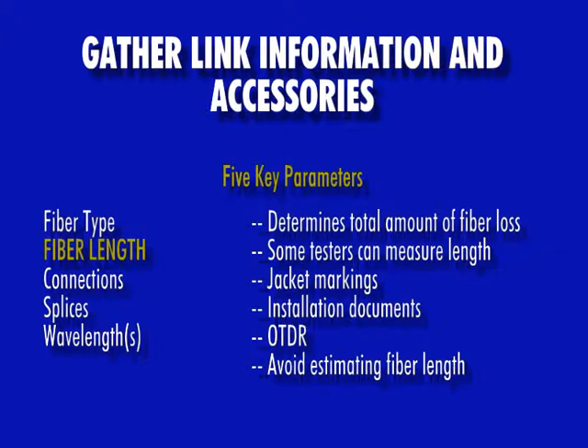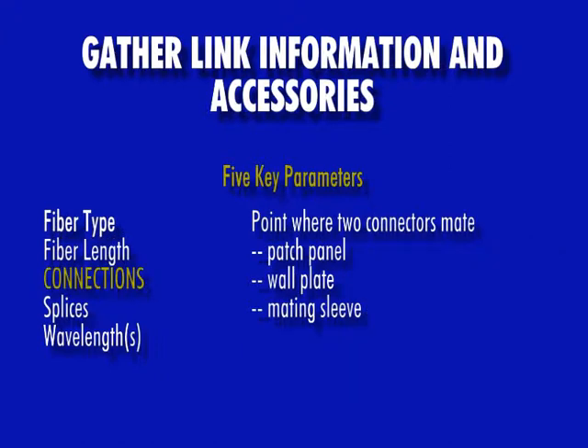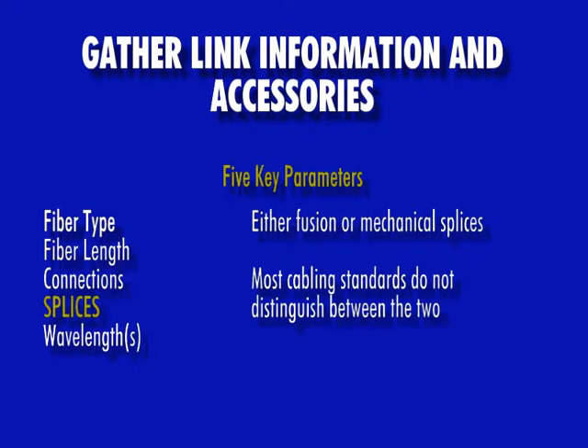For best results, avoid estimating the fiber length whenever possible. Third is number of connections — a connection is the point where two fiber connectors mate together, such as in a patch panel, wall plate, or mating sleeve. Fourth is the number of splices, which can be either fusion or mechanical.